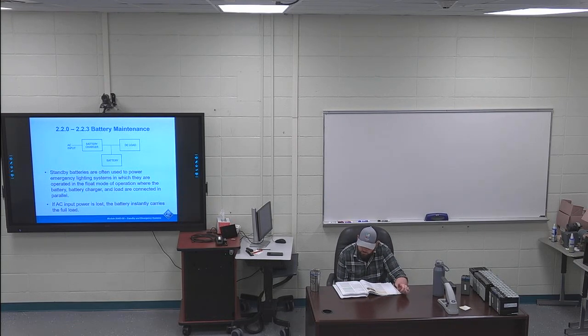Battery and battery charger operation. Right-hand side of page 15, the last two sentences of 223 are highlighted. Also note that a battery's charger output must be derated for altitude when it's installed at locations above 3,300 feet, and for temperatures when the ambient temperature exceeds 122 degrees Fahrenheit.